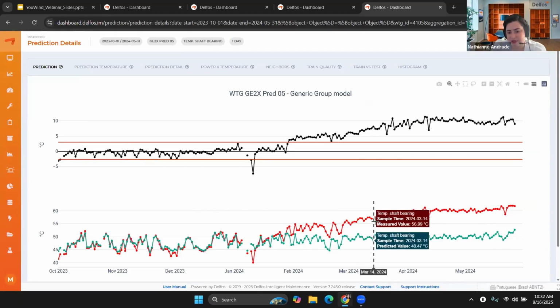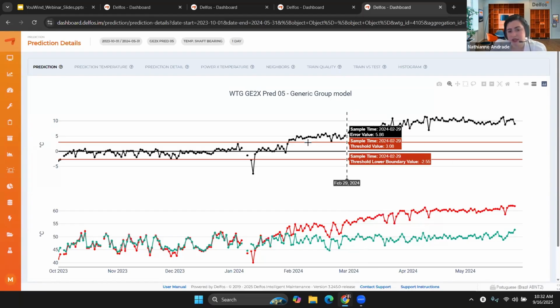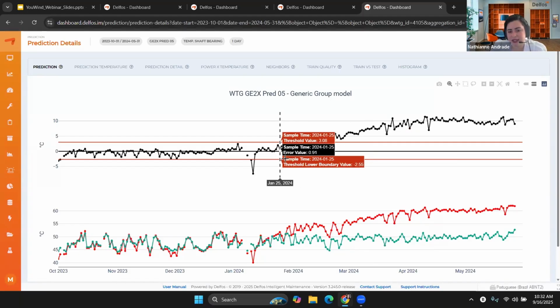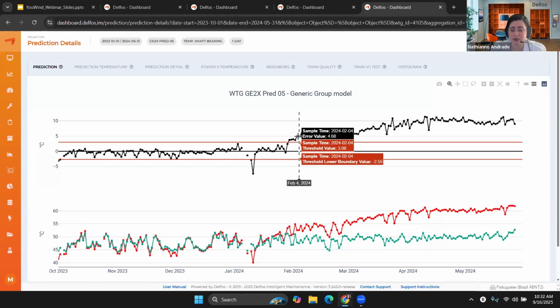You have the red time series, which is the measured temperature of the shaft bearing, and the green time series, which is the expected value calculated using machine learning models and all of the operation conditions relevant for this case, such as ambient temperature and active power. The difference between these 2 time series is the black time series above. When this difference is higher than the uncertainty of our machine learning models, we raise an alarm and warn you that there's a problem with your wind turbine before any downtime occurs.